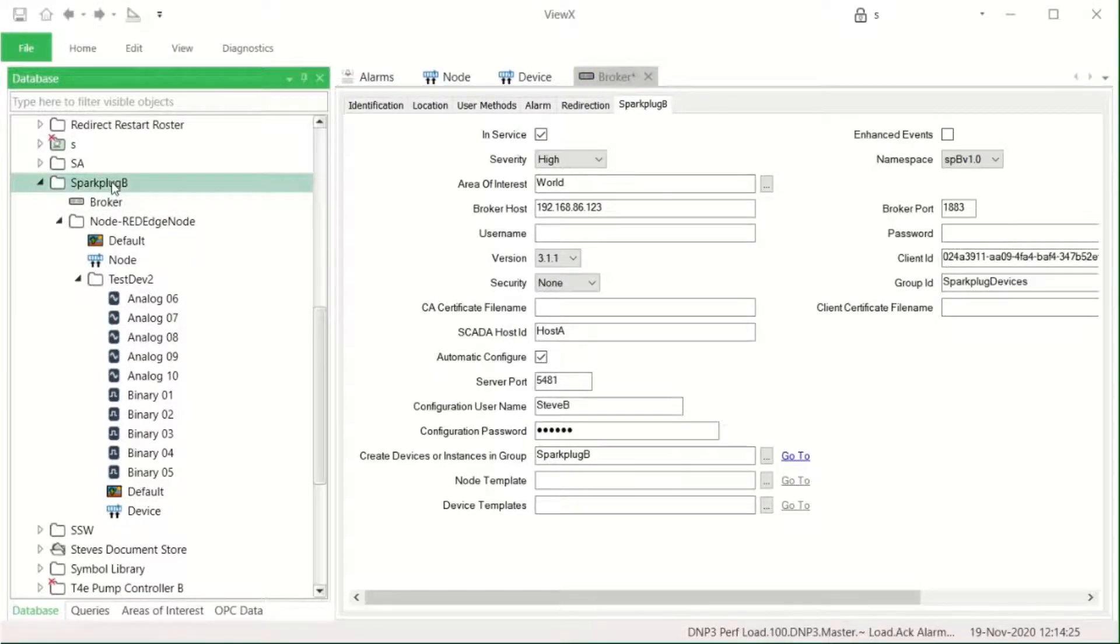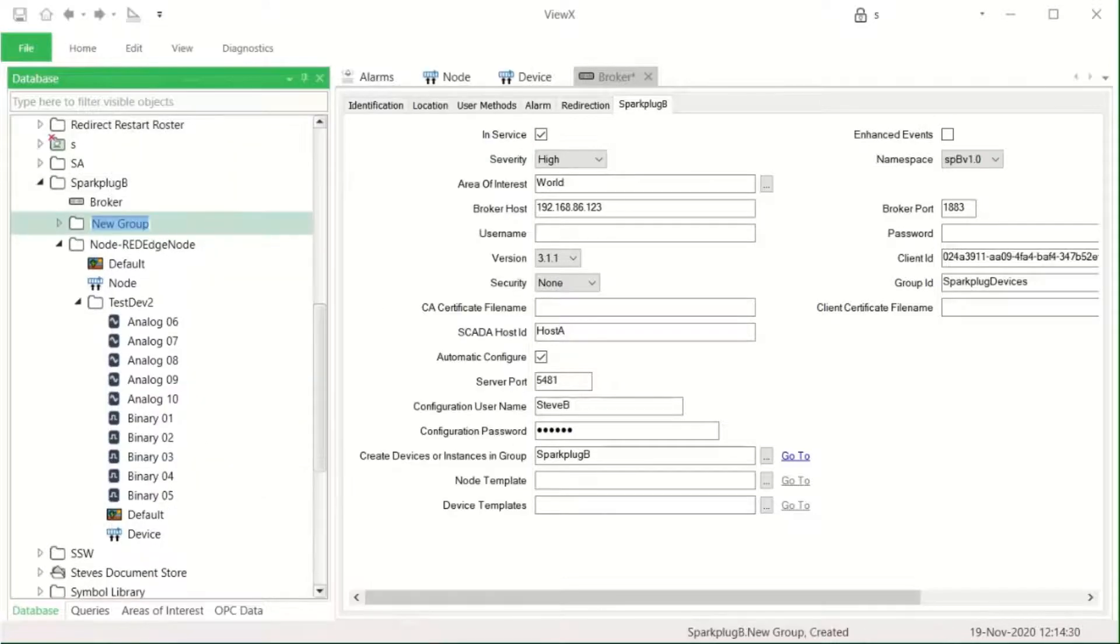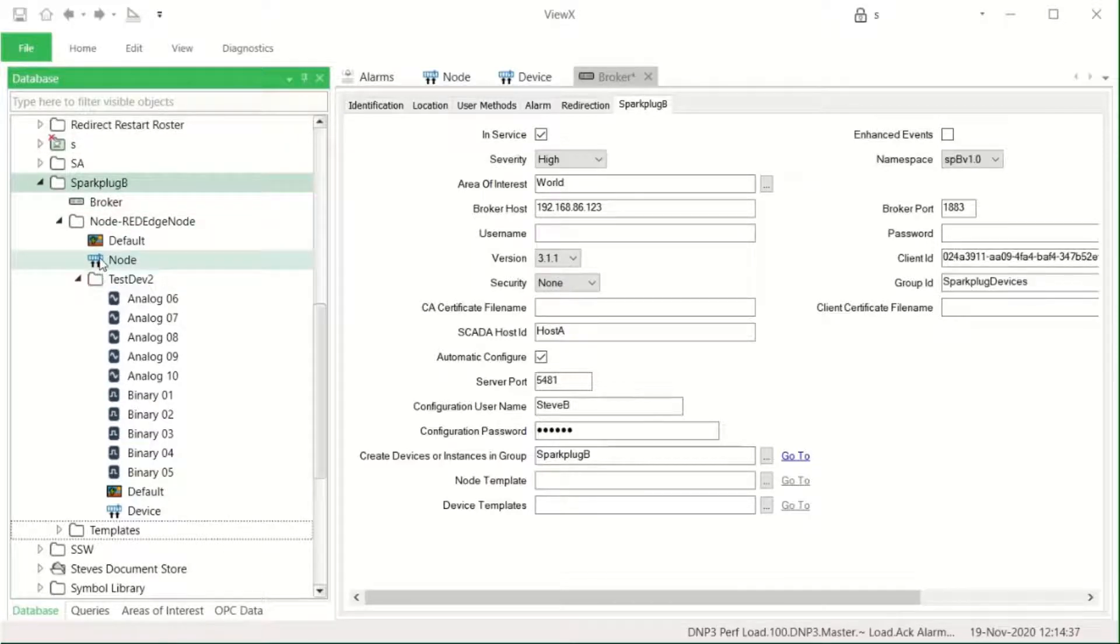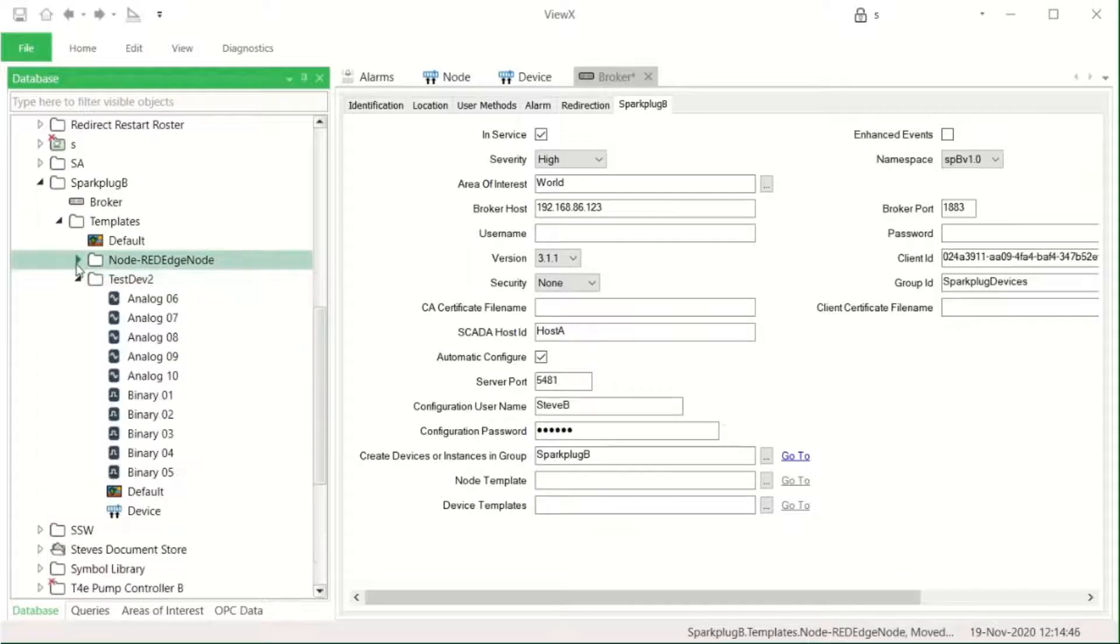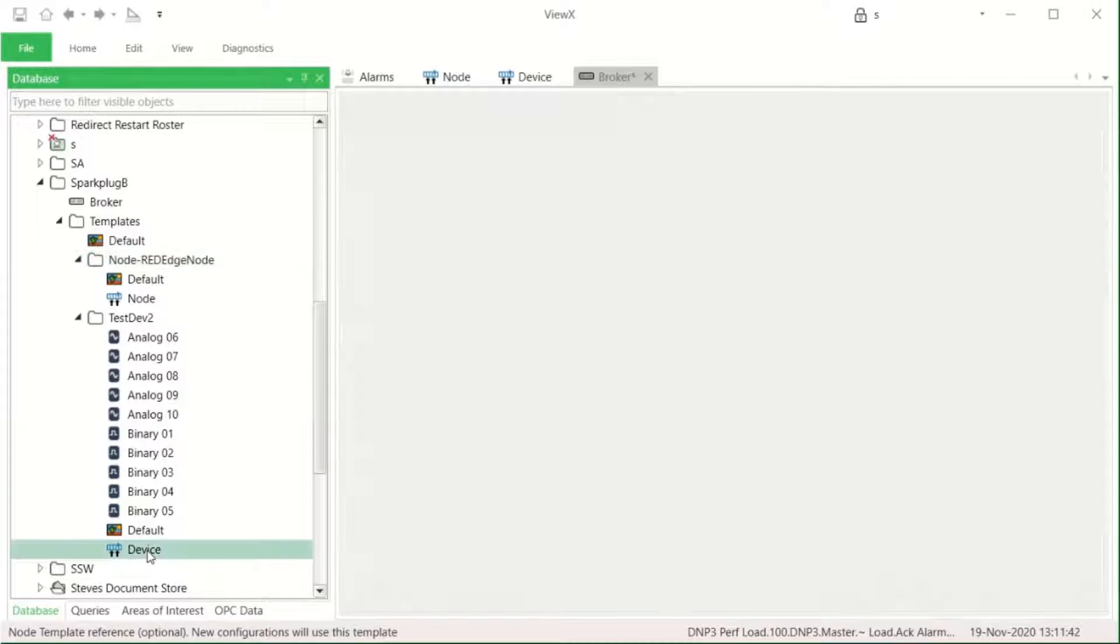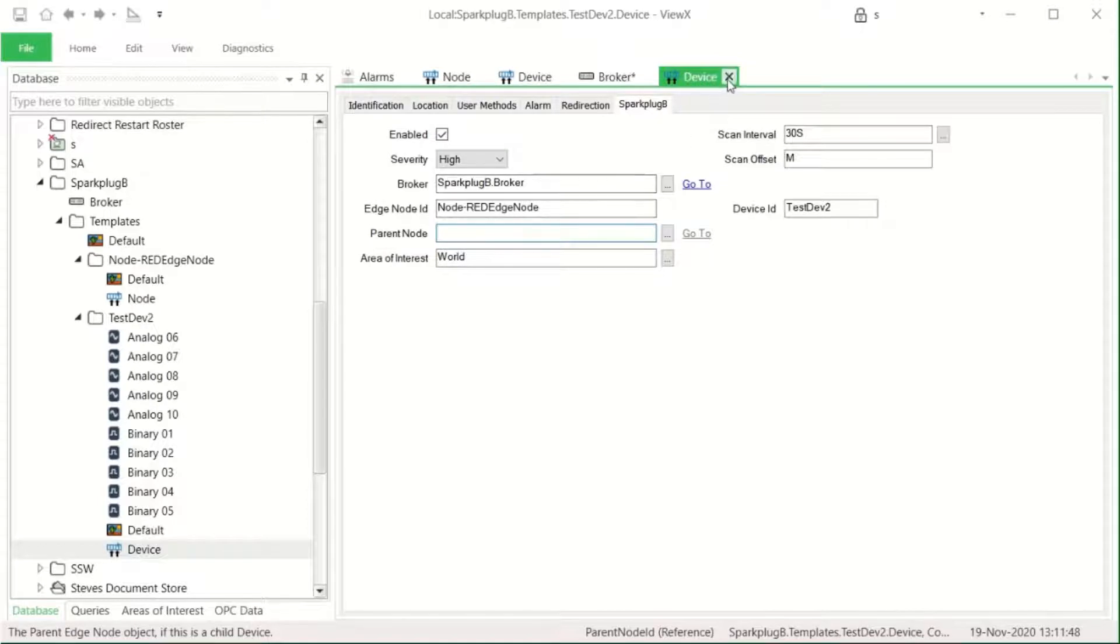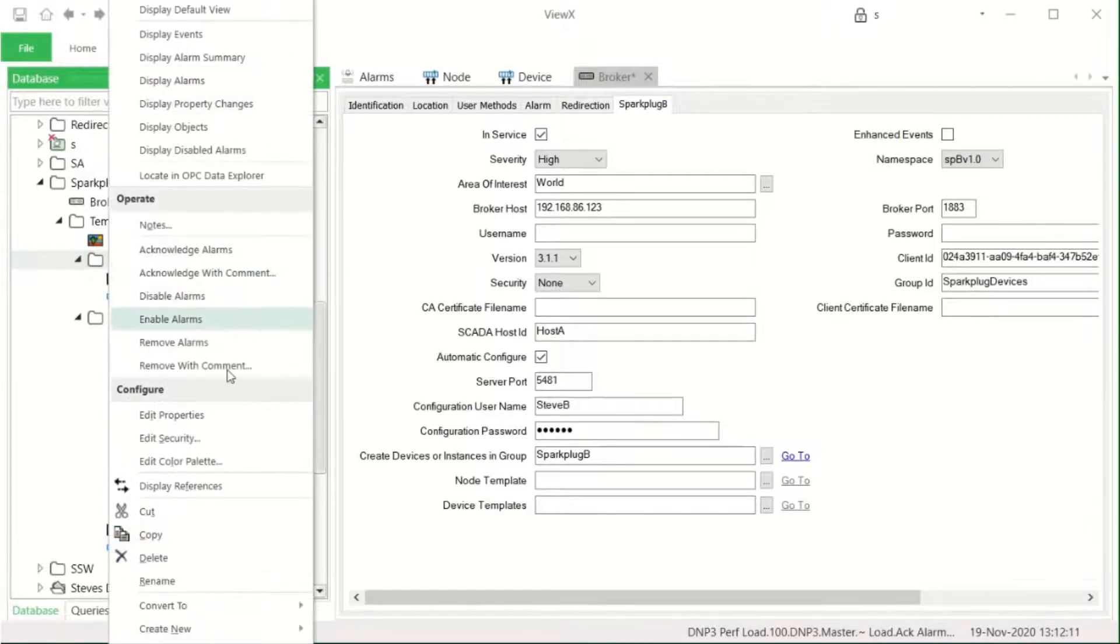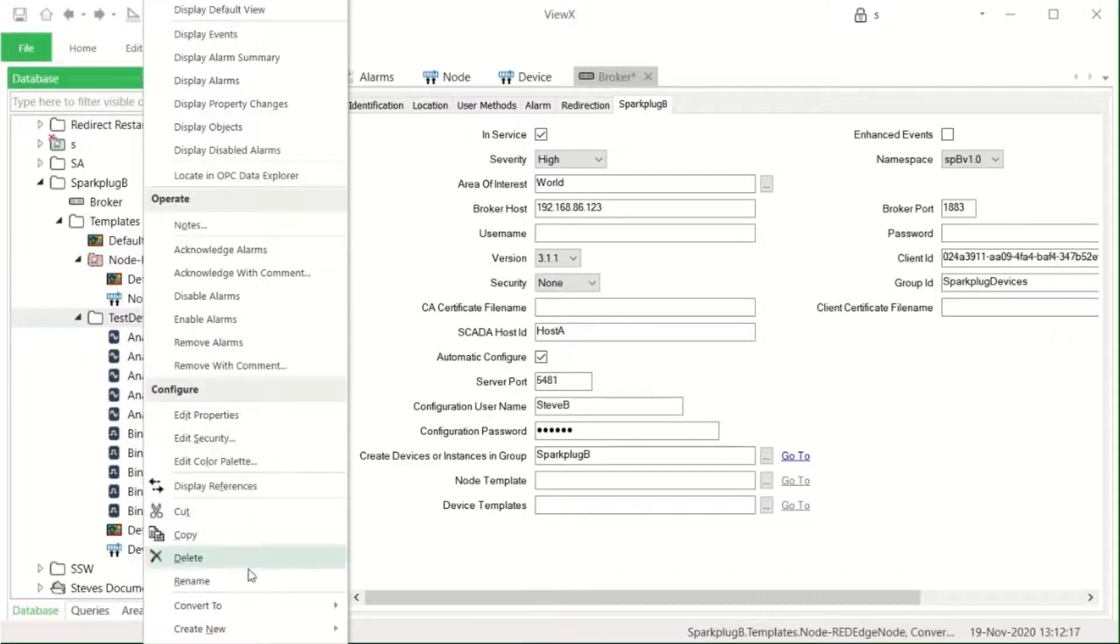Now to take automatic configuration to the next level, I'm going to set a couple more properties on the broker and then convert the configuration that we've received into Geo SCADA templates. These will control and extend new configuration. Start by moving each group into a templates group. Now I'm going to remove the node reference from the device. This is necessary for the template conversion. And then I perform the conversions into templates. Finally, add a link to the node template and to link to the group of templates into the broker object and save it again.